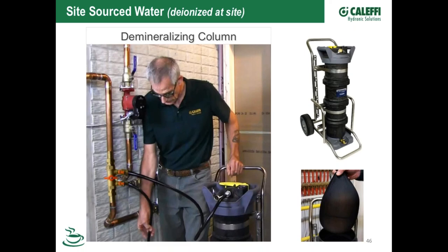So the bottom line is, even with demineralized water, you're going to have no problem with your low water cutoff. We had a couple of issues where people had a problem, but they just added a little bit of tap water and the conductivity quickly went up to where the low water cutoffs work perfectly. The day they were there, they wanted to get that back up so they didn't walk away from it questionable if it was right on the borderline.